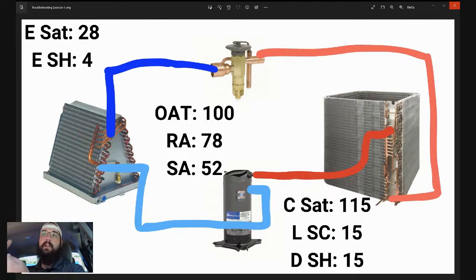We can do something to get them a little further, get some of that trash out of there. Anyway, we go through the process. Let's say we do that. We don't get it proper, but we get a lot of it out. It is in a much better condition than when we started. And we're going to see that saturation come up. That superheat's going to start to come up. That discharge superheat's going to start to come up as well. Our supply air is going to start to come back up a little bit.